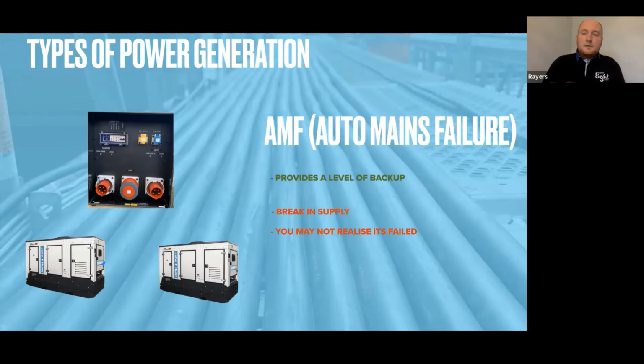But then the power comes back on within 20 seconds and they don't really think of anything. They don't think to tell anyone, and they just carry on as usual. In a very unlikely situation, if you're very unlucky, the runner or the standby machine then fails in due course over the weekend perhaps, or there's an issue with it and nobody's realized. And then of course you get the phone call, or the radio call, to say we've lost power, at which point you go to find 2 dead generators.